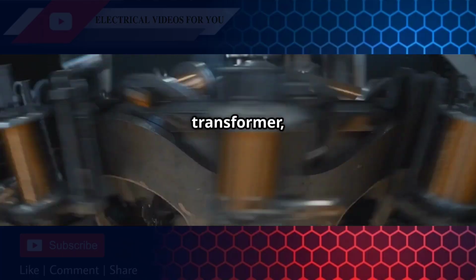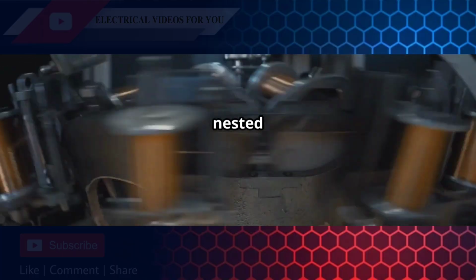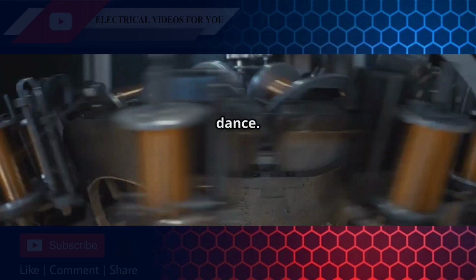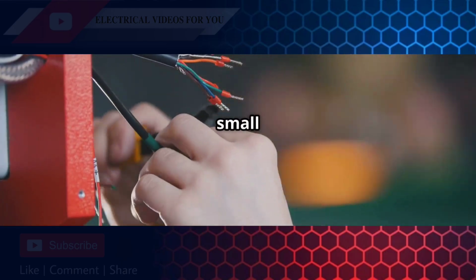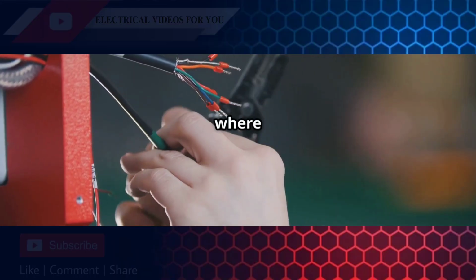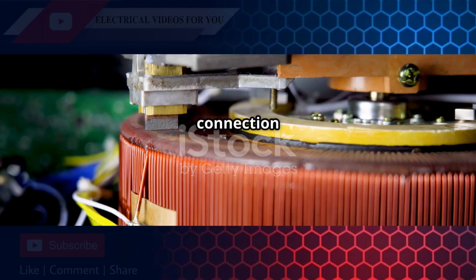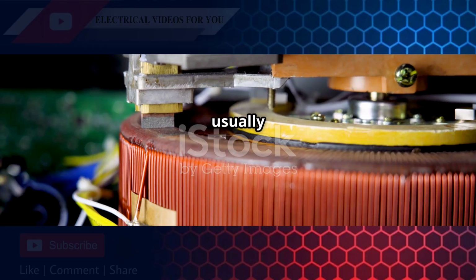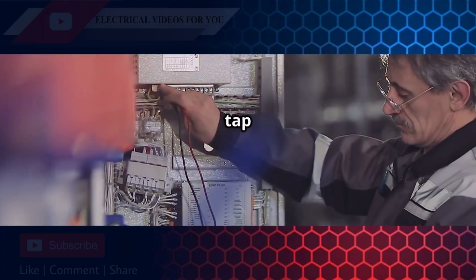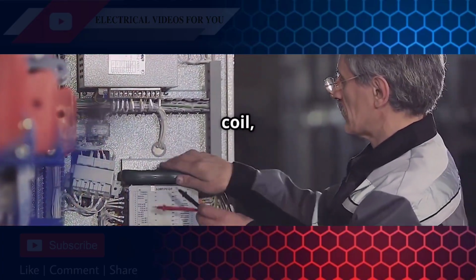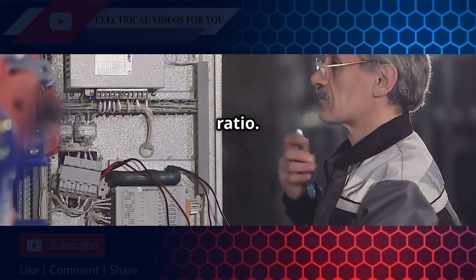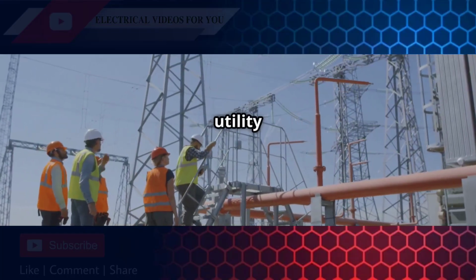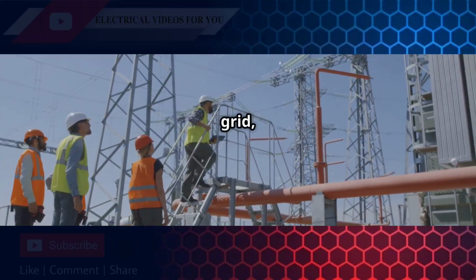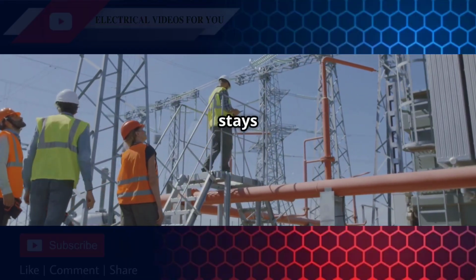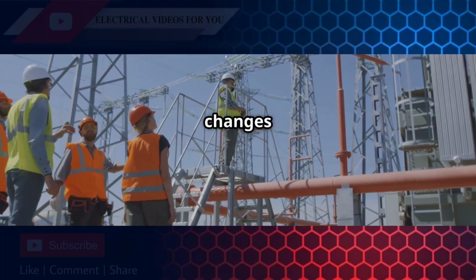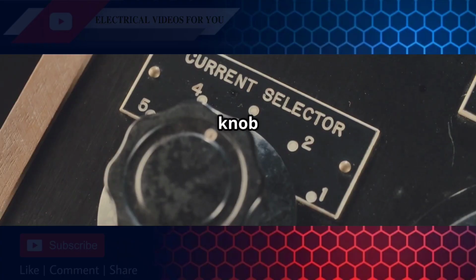So the next time you see a transformer, you can imagine those two coils, nested together but not touching, doing their electrical dance. Sometimes, we need to make small adjustments to the output voltage. That's where tappings come in. Tappings are extra connection points, or taps, on the windings, usually on the high voltage side. By changing which tap is connected, we can change the number of turns in the coil, which in turn slightly changes the voltage ratio. This is incredibly useful for utility companies to fine-tune the voltage in the power grid, ensuring that the power delivered to your home stays stable, even if the load on the system changes throughout the day. It's like having a volume knob for voltage.